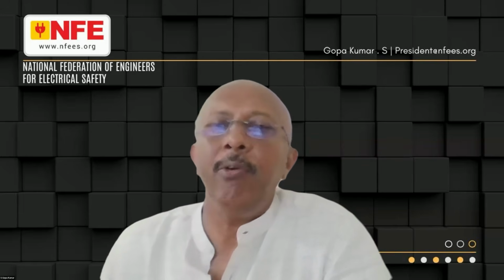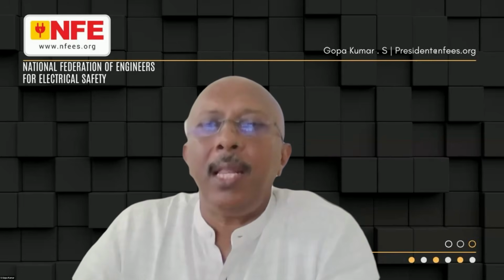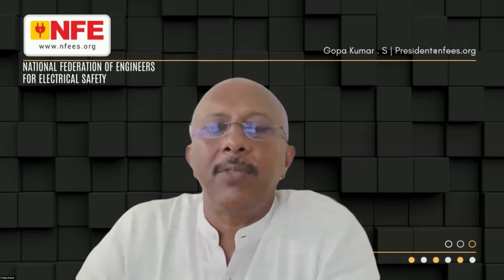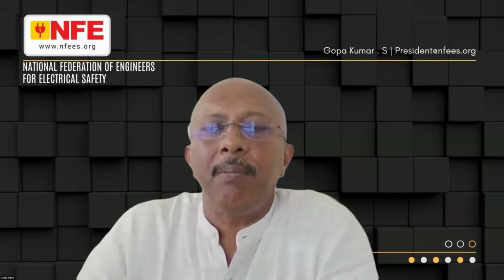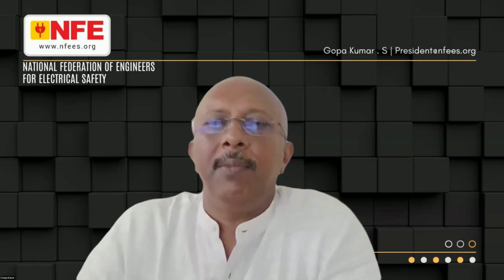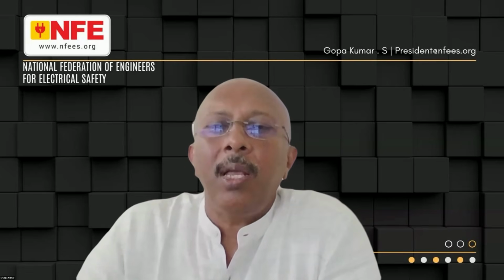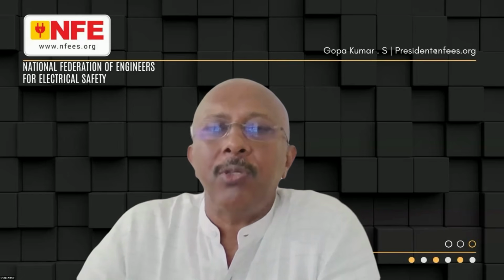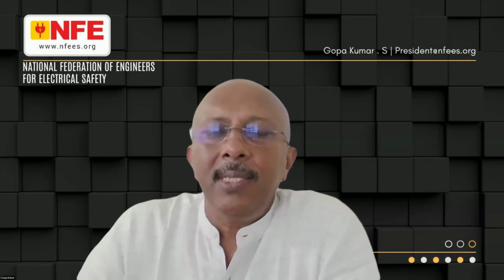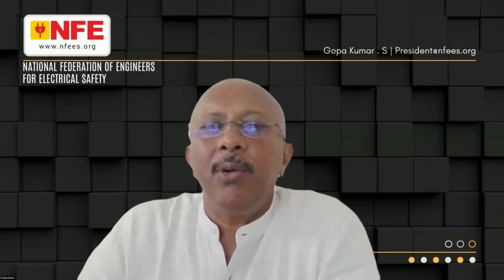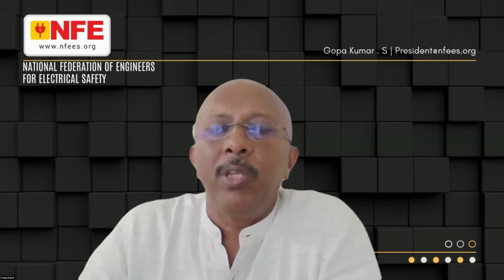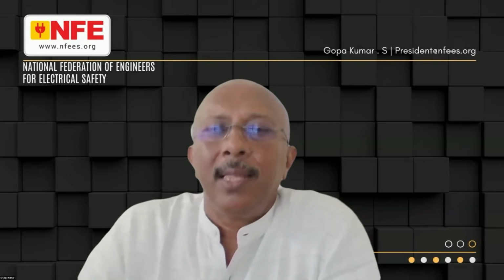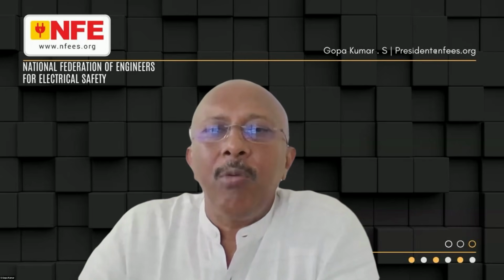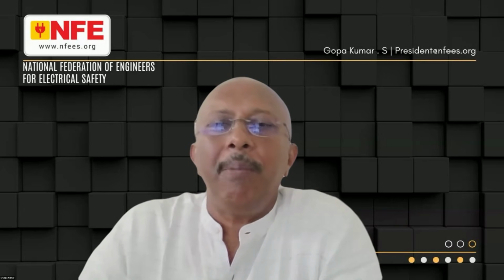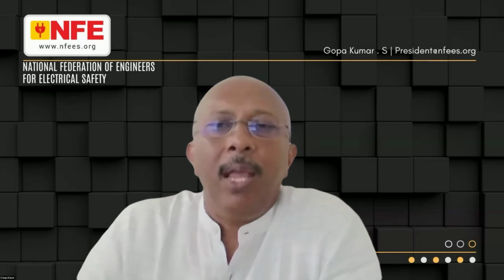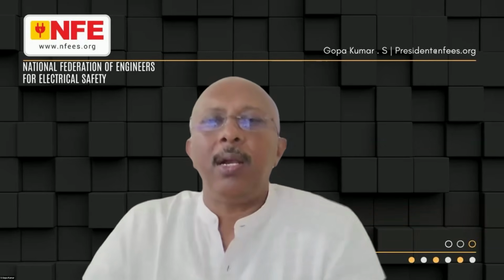Please note, a huge earth fault current will flow on the low voltage side of the system during a fault on the low voltage side, provided you have a TN system. If you have a TT system, the fault current will be limited to a few amperes or a few tens of amperes. TT system means your transformer neutral is separately connected to an earth electrode, and your electrical main distribution board is connected to a separate earth electrode. Under that condition, the maximum earth fault current will be limited to a few amperes or a few tens of amperes, maybe 10 ampere, 20 ampere.